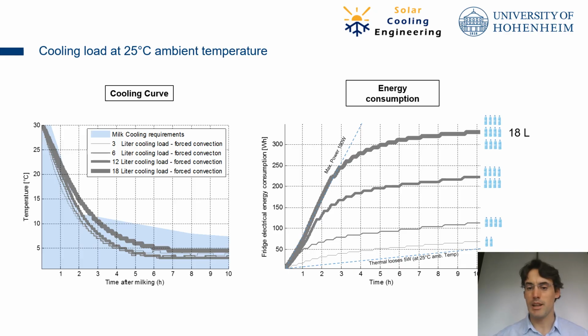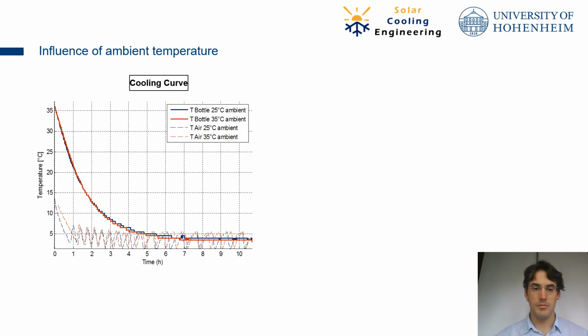Yeah, and once the product has been cooled down, then you see the energy consumption is increasing quite slowly, and this is because of the thermal losses. So in the energy consumption of the refrigerator, you have always a portion of cooling power that is delivered to the product that you are putting inside, and another part is the thermal losses that you have continuously there, and that depend only on the ambient temperature. Okay. And now let's have also a look to the influence of the ambient temperature on the cooling curve, and later on the energy consumption.